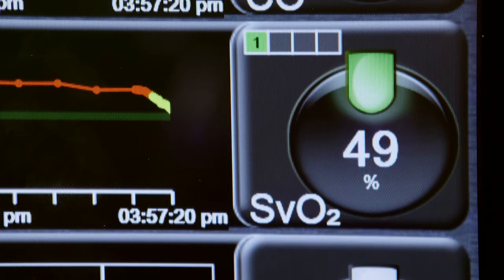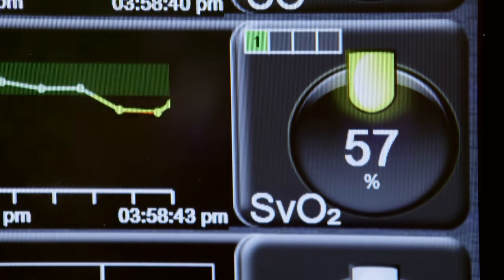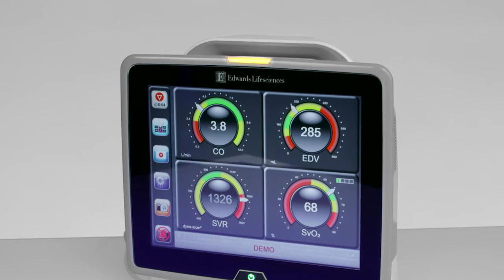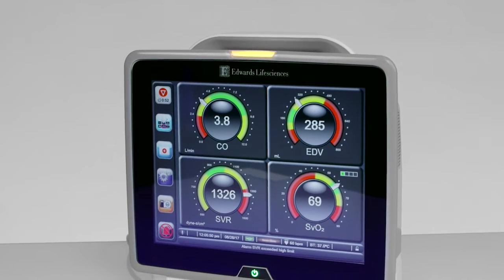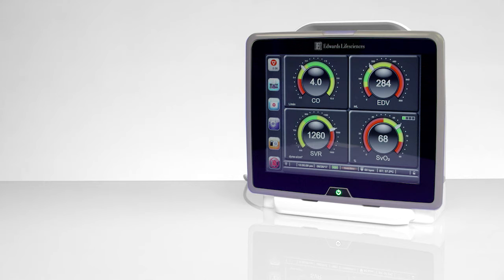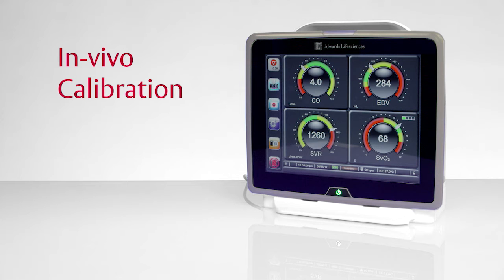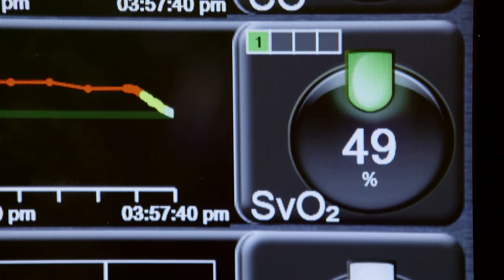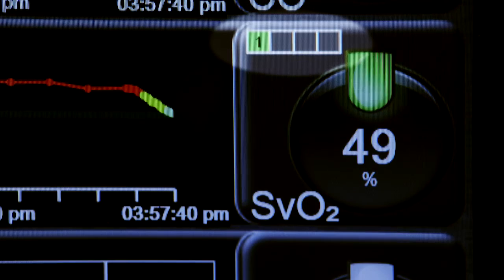If the SVO2 reading falls outside of the bounds set for that parameter, a yellow warning light on the readout will appear, and the amber warning light at the top of the HemoSphere Advanced Monitor will illuminate. While the in vitro calibration is performed only once at the start of each monitoring session, the in vivo calibration should be performed at least once every 24 hours. During in vivo calibration, the SVO2 signal quality index should be green, confirming a stable signal.